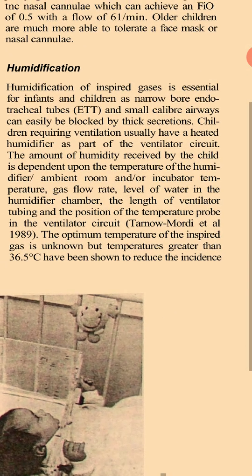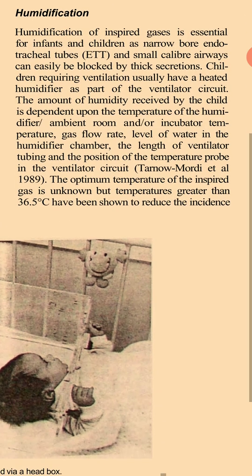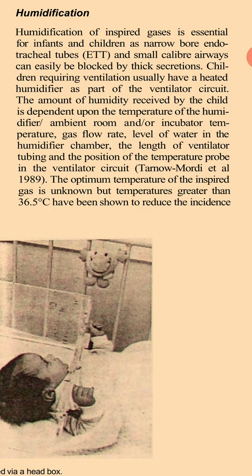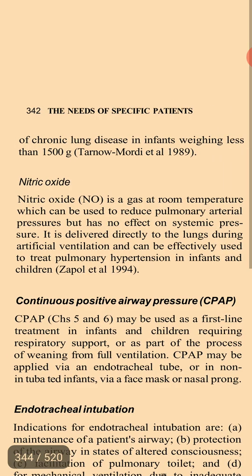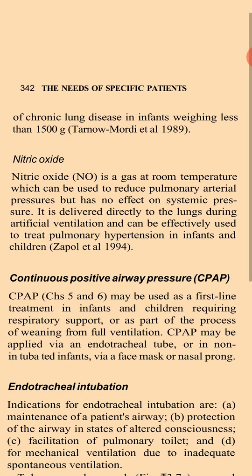Humidification of inspired air is essential for infants and children as narrow bore endotracheal tubes (ETT) and small caliber airways can easily be blocked by thick secretions. Children requiring ventilation usually have a heated humidifier as a part of the ventilator circuit. The amount of humidity received by the child is dependent upon the temperature of the humidifier, ambient room and or incubator temperature, gas flow rate, level of water in the humidifier chamber, the length of ventilator tubing, and the position of the temperature probe in the ventilator circuit. The optimum temperature of the inspired gas is unknown, but temperatures greater than 36.5 degrees Celsius have been shown to reduce the incidence of chronic lung disease in infants weighing less than 1,500 grams.